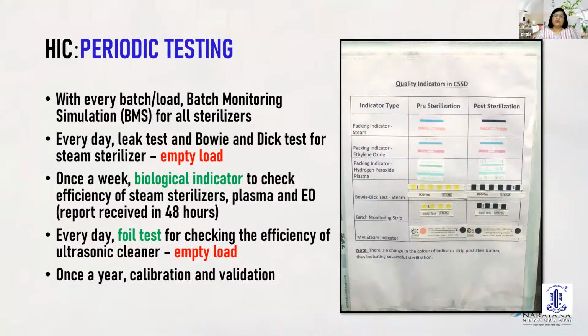Periodic testing. Now, this is also a very important part when it comes to the quality indicators in CSSD. With every batch and load, BMS simulation is done for all sterilizers. Then you have everyday tests. Every day we have a leak test and a Bowie-Dick test for the steam sterilizer on an empty load. Once a week, we do a biological indicator to check the efficiency of steam sterilizers, plasma, and EO, which is the report received in 48 hours. Every day, a foil test for checking the efficiency of the ultrasonic cleaner is done on empty load. And once a year, calibration and validation of the machines is done.